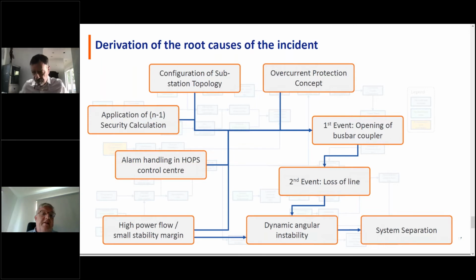We need to look at alarm handling. We put HOPS here, but I think it's more general - we need broader rules on when to start reacting to alarms. If a busbar coupler, in this case, or a line is loaded at 80%, is that okay, or do we need to start reacting at 90%? We really need to react then, because at 100%, the protection disconnects and it's too late.